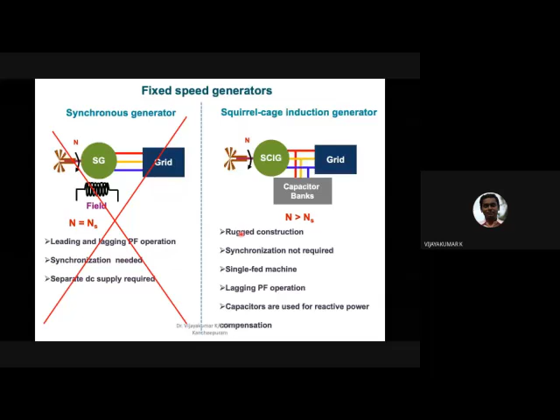So normally they prefer squirrel cage induction machines for fixed speed wind turbines, right? We can even say 80% of wind turbines are based on this. When you use this same induction machine for supplying standalone loads, that topology is called the self-excited induction generator. Without a capacitor, if you connect this squirrel cage induction machine to loads, it won't provide the supply, because there is no field coil available, so you are not exciting this machine. That's why you use the capacitor. By connecting the capacitor, if you rotate that machine at a particular speed, because of the residual magnetism, or the residual voltage, the voltage will build up in the stator coils and be supplied to the loads.